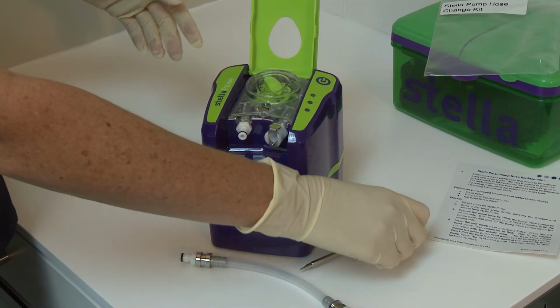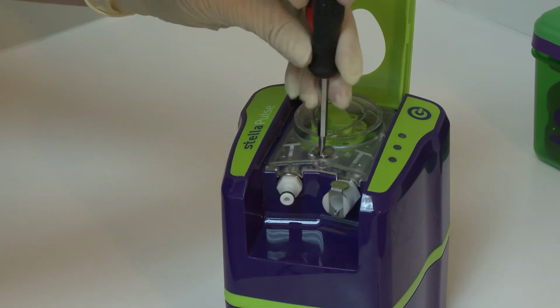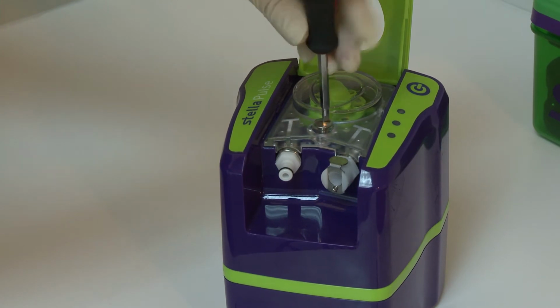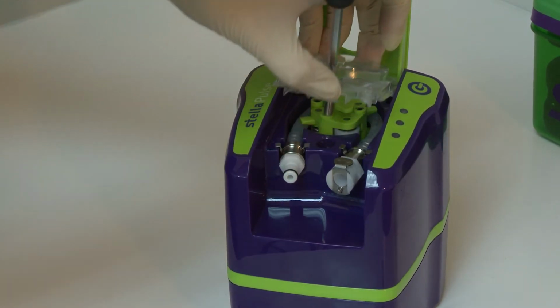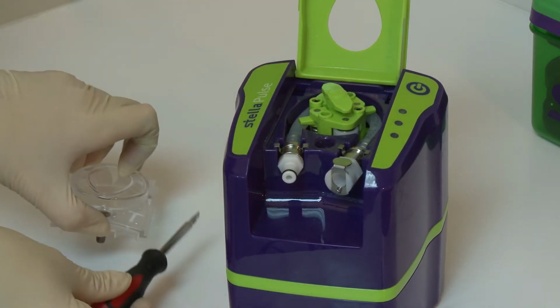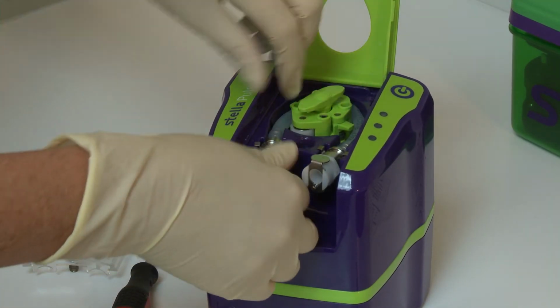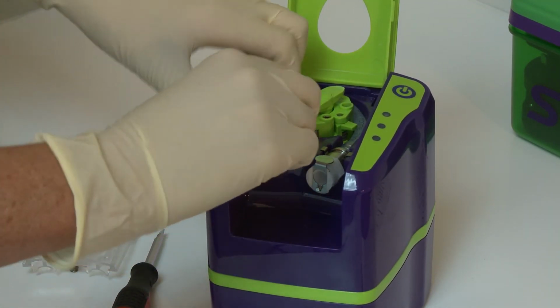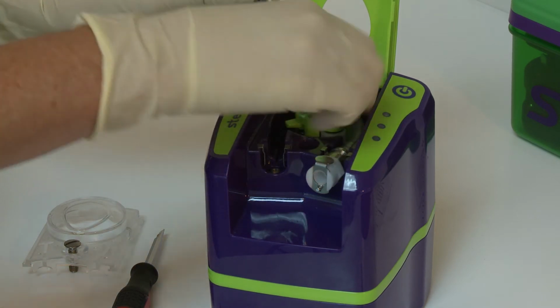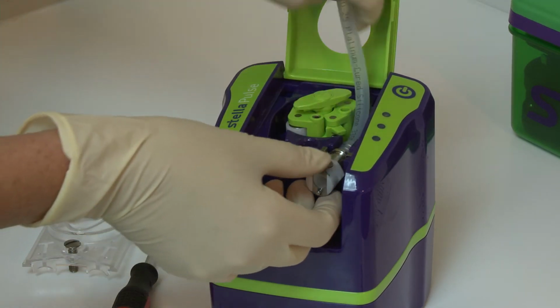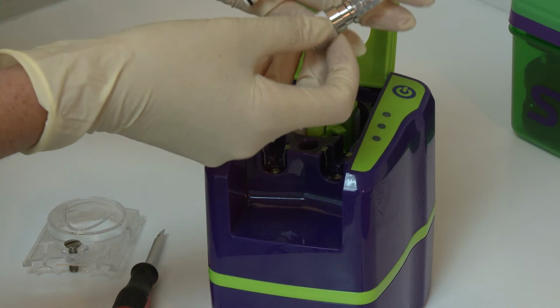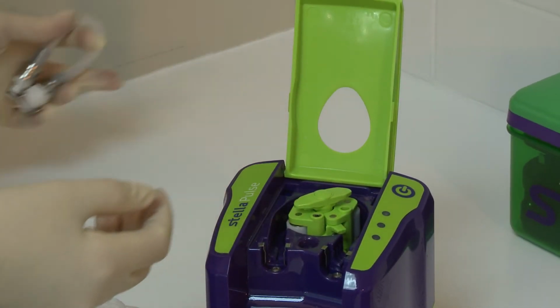1. Lift the cover on Stella Pulse. 2. Unscrew the window and remove the window from Stella Pulse using a flathead screwdriver. 3. Remove the pump hose by lifting the pump hose connector on the left side. Turn the green pump head clockwise to lift the curved hose, and then lift the pump hose connector on the right side. Discard the used pump hose.